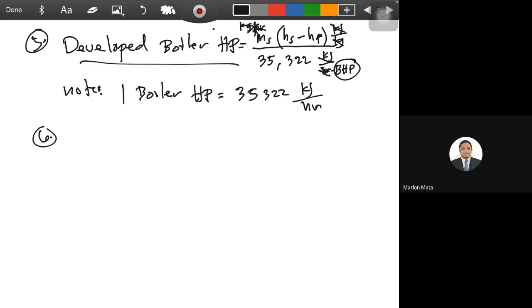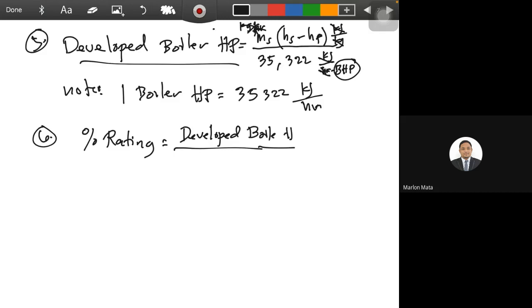So formula number six is percent rating. The percent rating of boiler is equal to the developed boiler horsepower divided by the rated boiler horsepower, which is the RBH, computed using the heating surface area. So again, they will have the same unit of horsepower. So technically, they will cancel out, creating only a constant. Percent rating. Okay.